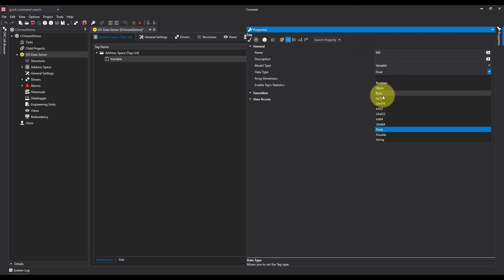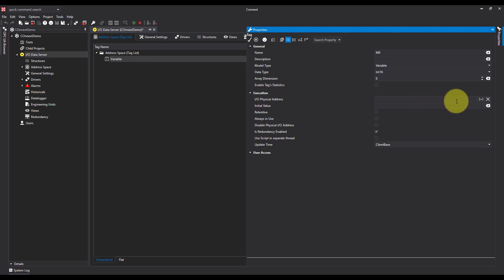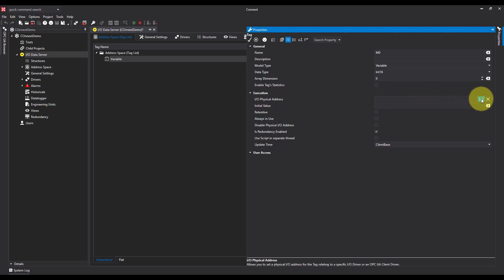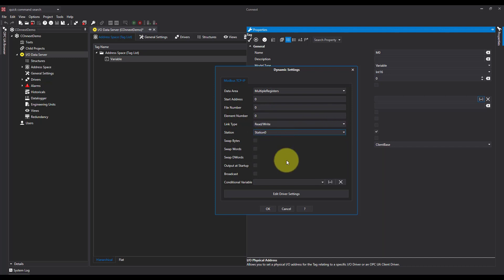I'm going to make it an integer. And then under execution, I want to find my IO physical address. Go to my settings, I know it's multiple registers, which is what I want. I can see the start address is 0, and the station, which is set as station 0.